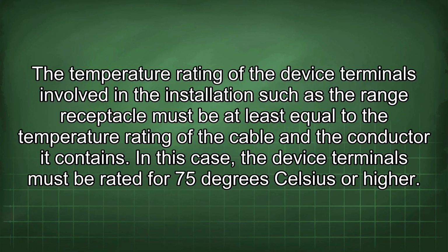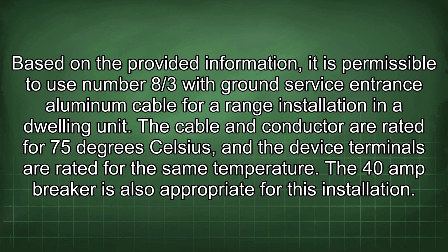The temperature rating of the device terminals involved in the installation, such as the range receptacle, must be at least equal to the temperature rating of the cable and the conductor it contains. In this case, the device terminals must be rated for 75 degrees Celsius or higher. Based on the provided information, it is permissible to use number 8/3 with ground service entrance aluminum cable for a range installation in a dwelling unit. The cable and conductor are rated for 75 degrees Celsius, and the device terminals are rated for the same temperature. The 40 amp breaker is also appropriate for this installation.